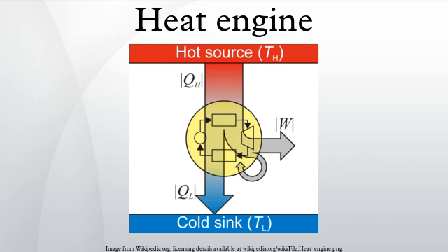Exploit the physical properties of the working fluid. The most common such exploitation is the use of water above the so-called critical point, or so-called supercritical steam. The behavior of fluids above their critical point changes radically, and with materials such as water and carbon dioxide it is possible to exploit those changes in behavior to extract greater thermodynamic efficiency from the heat engine, even if it is using a fairly conventional Brayton or Rankine cycle. A new and very promising material for such applications is CO2. SO2 and xenon have also been considered for such applications, although SO2 is a little toxic for most.